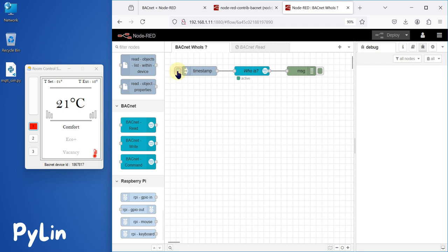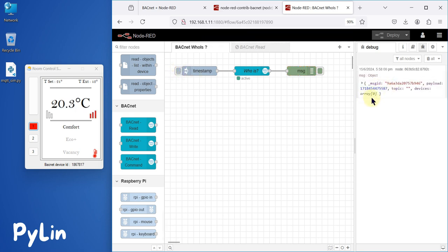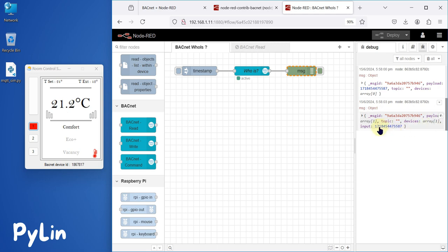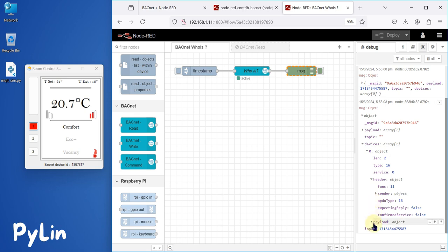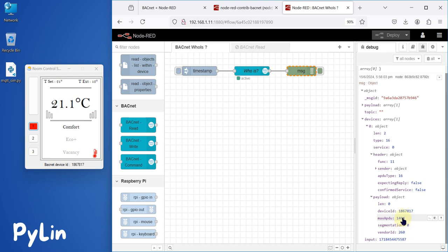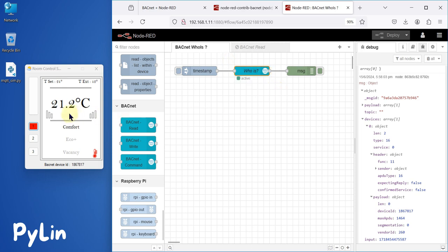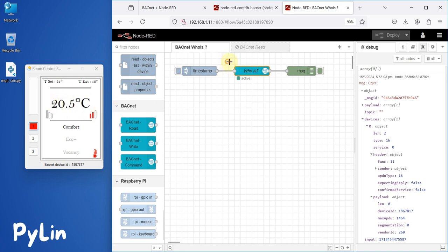Once you configure everything and click Inject, you will first see Array 0 — no device found — and then Array 1, meaning a device was found. It sends two WHO-IS requests and on the second request you get your device. Expanding the payload under the devices object, you can see the device ID is 1867817, which matches the device ID shown in the Room Controller Simulator. The device has successfully responded to the WHO-IS request, indicating it is available for data exchange.